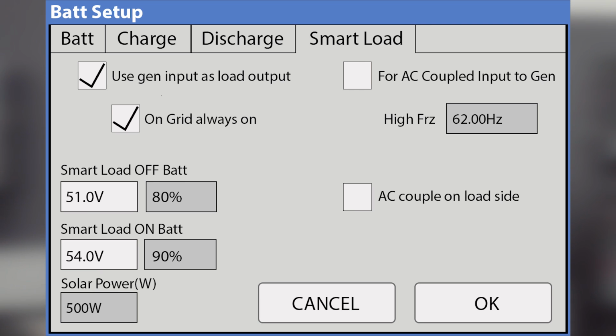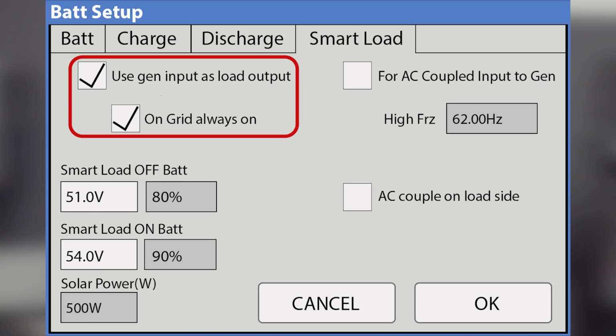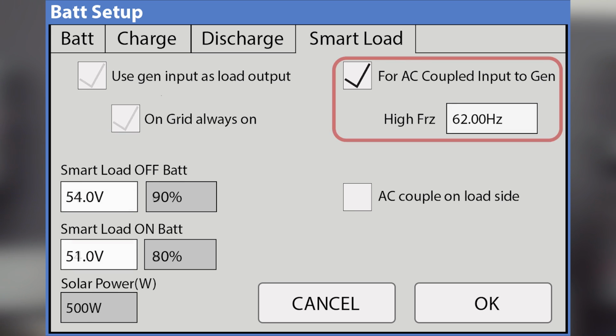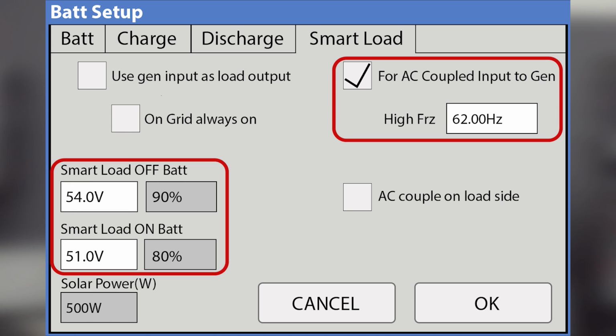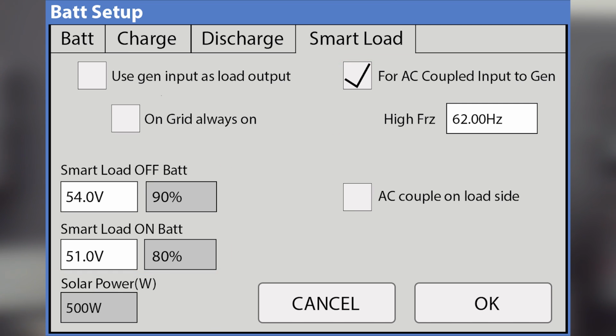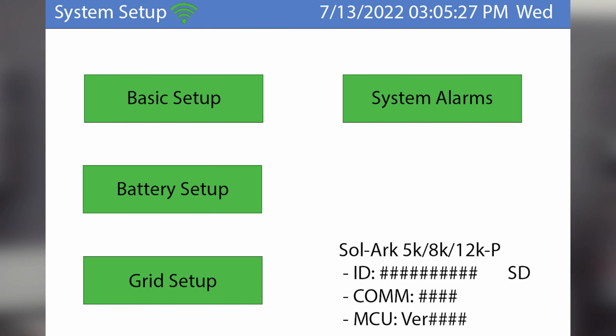Gotcha, very cool. You kind of use the same boxes. The text here doesn't actually change if you go between load output and AC coupled input, which can be a little confusing. So just know the text doesn't change, but the meaning of the box does. In load output mode, it works just as described. In AC coupled mode, these set points are kind of reversed, because you want the AC coupled panels to turn off before you get to full battery, and then back on again as you get lower. As opposed to with a load, you want it to be the reverse. So just know that, and that sums up the battery setup tab.